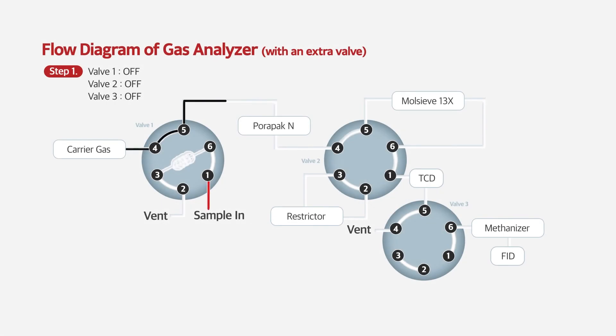When all valves are off, the sample is loaded in the loop. Turning on valve one, the sample flow is switched for injection. As described previously, hydrogen and oxygen are eluted earlier in Porapak N column, separated in molecular sieve column and detected by TCD.